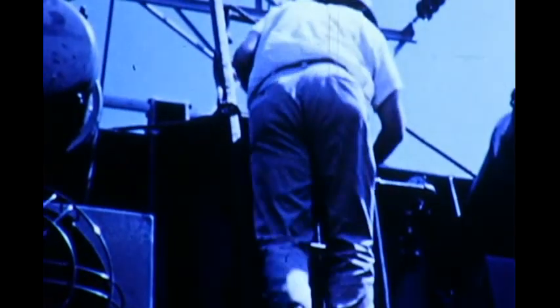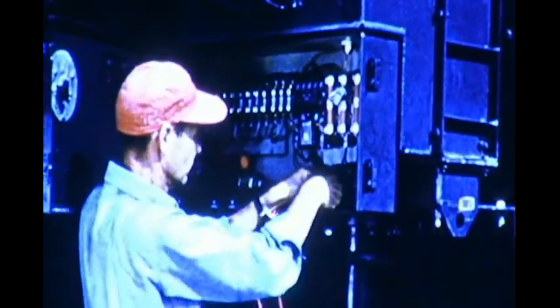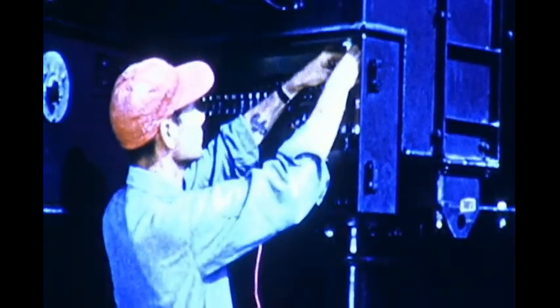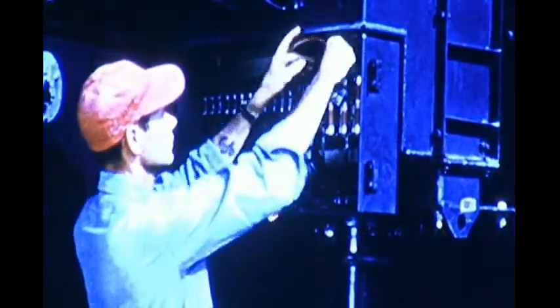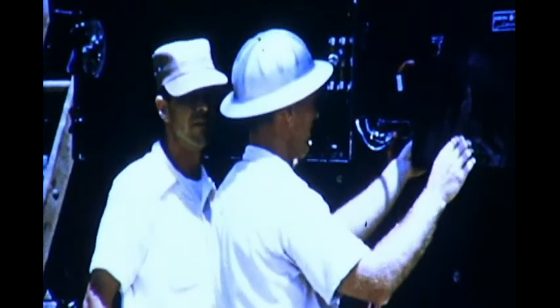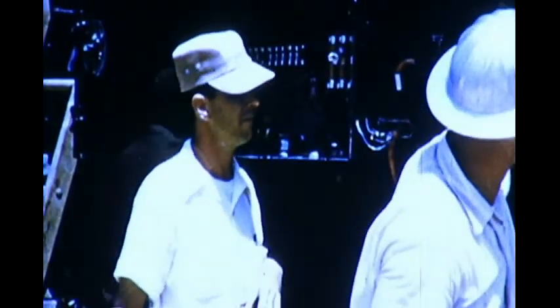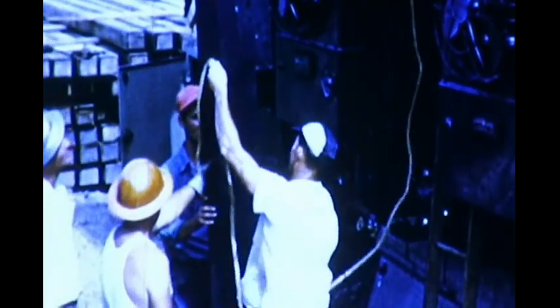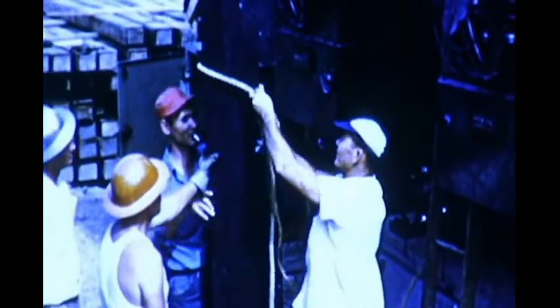Once this is done, oil filling under vacuum goes ahead. During the filling, we can proceed with other phases of the installation. For instance, there's the job of connecting the pre-wired control devices on the unit coolers to the conduit on the transformer. Also, winding and oil temperature equipments must be installed. And baffles mounted. The baffles assure that all fans get a continual supply of fresh, cool air.